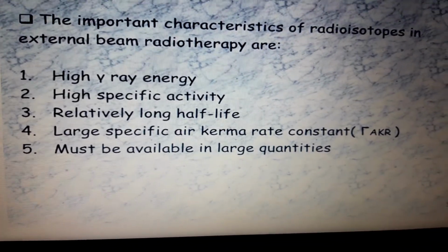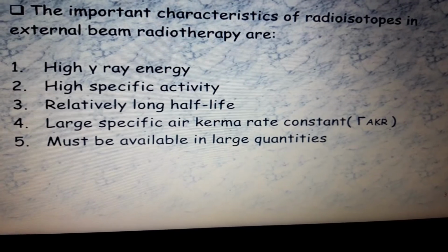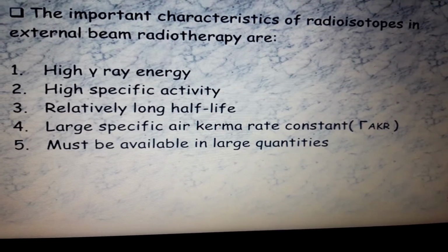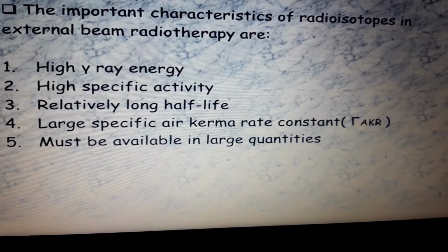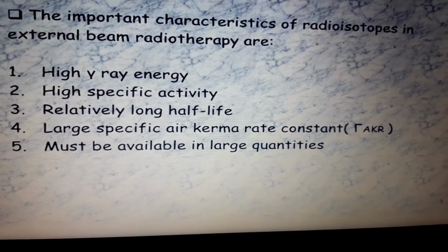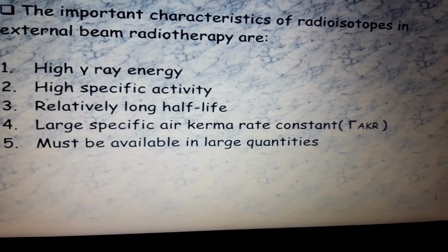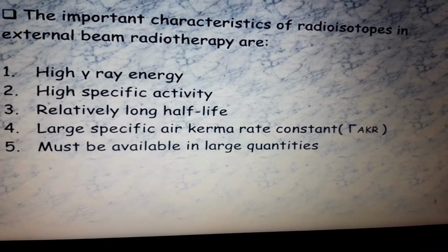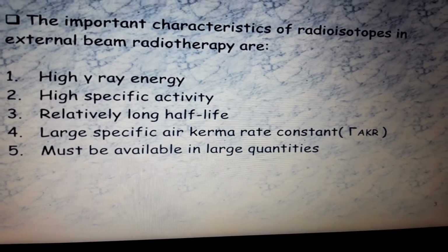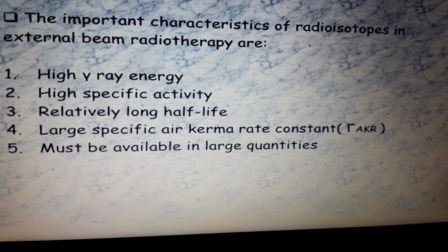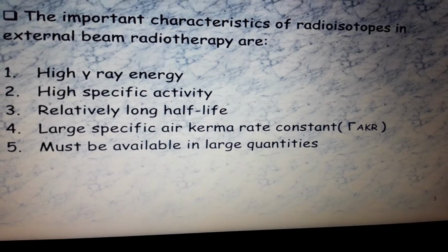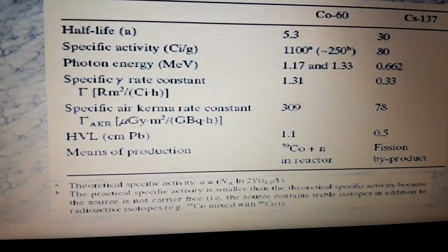The most important characteristics of radioisotopes in external beam radiotherapy are: number one, high gamma ray energy, high specific activity, relatively long half life, large specific air kerma rate constant, and it must be available in large quantities.